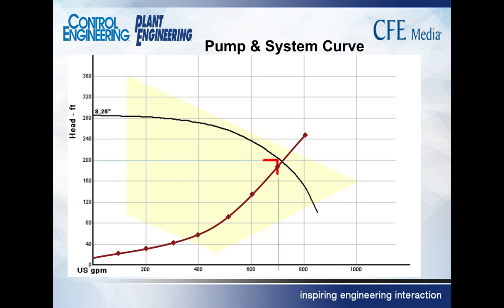Let me clean it up a little bit and make it a little clearer. In this particular illustration, if you look at the horizontal axis, our operating point occurs at about 700 gallons per minute. Let's suppose, for illustration purposes, that that's a little bit too much. You know what? We're pumping beer. This is a brewery, and the brewmaster says, you can't pump that at 700 gallons per minute. It's effervescing too much. We're going to end up with flat beer. Slow it down. He says, don't pump any more than 600 gallons per minute. I don't know why anybody would want to pump less beer, but that's what he says. So we need to get that back to 600 gallons per minute.